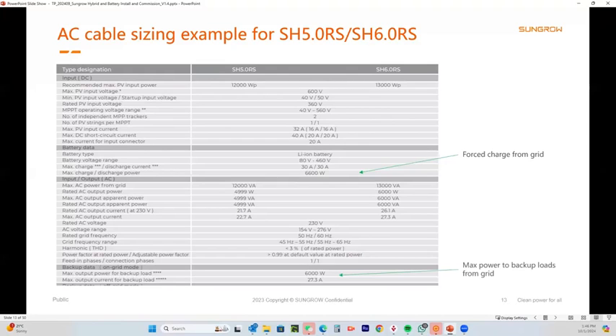They could also possibly have the backup loads maxed up at 6 kilowatts, which is another 27.3 amps. Now, that power, if there's no PV and they're charging the battery, that total power will be coming from the grid. And you can see here, in the case of the SH5RS, that's 12 kilowatts there. So that's something like 57 amps could be coming through that AC cable. So you do need to size that AC cable just in case this scenario happens. So please consult your standards as to what size of cable and cable protection you will use.